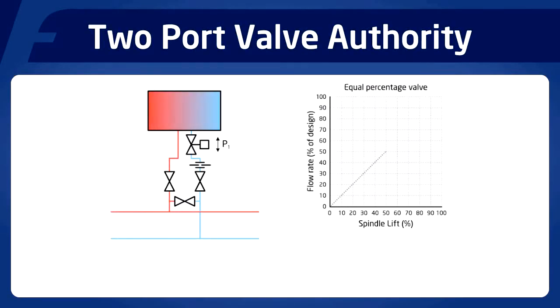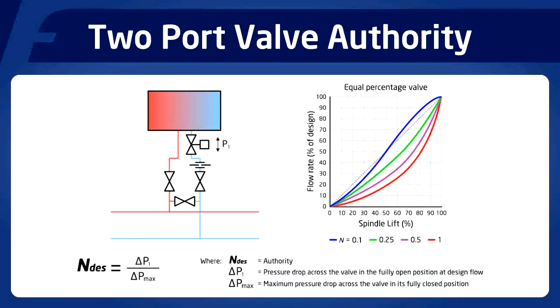The authority of a two-port control valve is the ratio between the pressure drop across the valve in the fully open position at design flow relative to the maximum pressure drop across the valve in its fully closed position. As we can see from the diagram and the graph, if we are able to size the kV of the control valve very low, then the authority could approach 1. But of course, this means a small valve with very high resistance.